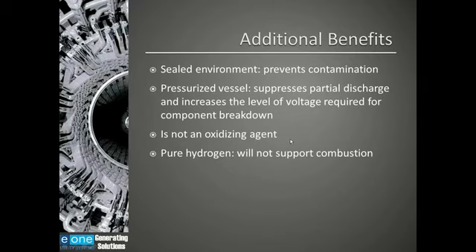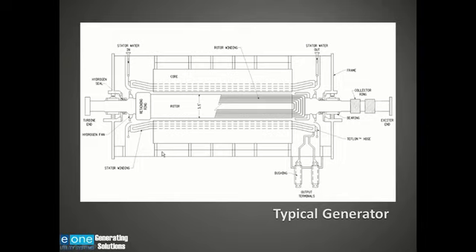One of the problems with using hydrogen is you have to keep it in the generator case. And because hydrogen molecules are so small, they are hard to contain. This slide indicates a sectioned view of a hydrogen-cooled generator. The outer shell is what seals the hydrogen in the generator. One area that is most difficult to seal the hydrogen is around the part that rotates, or the rotor. So here at each end of the generator there are seals that will seal the hydrogen in the generator.